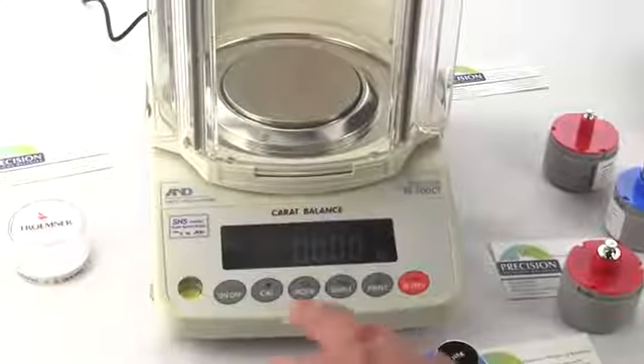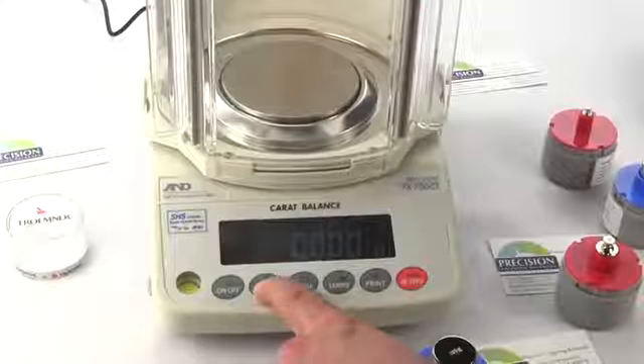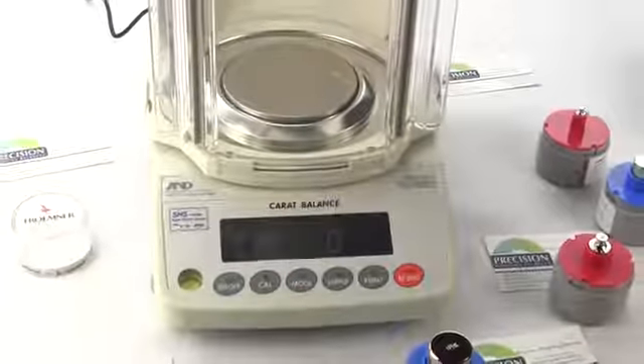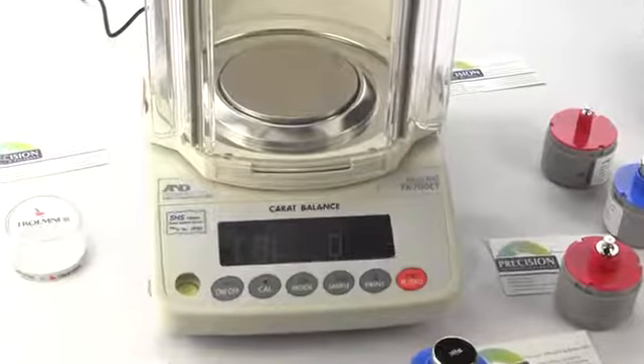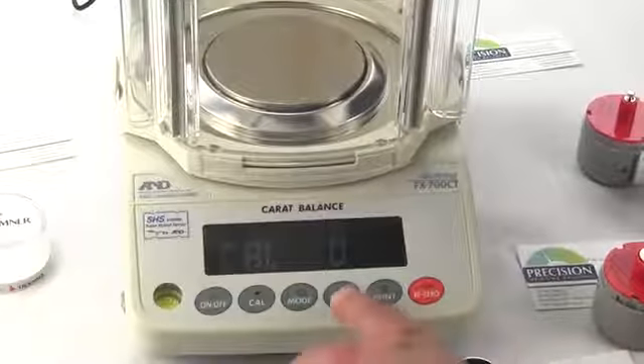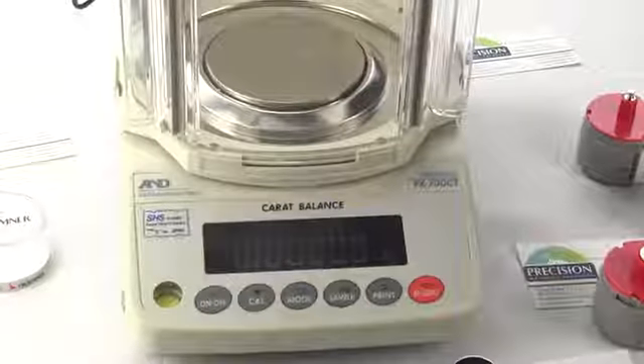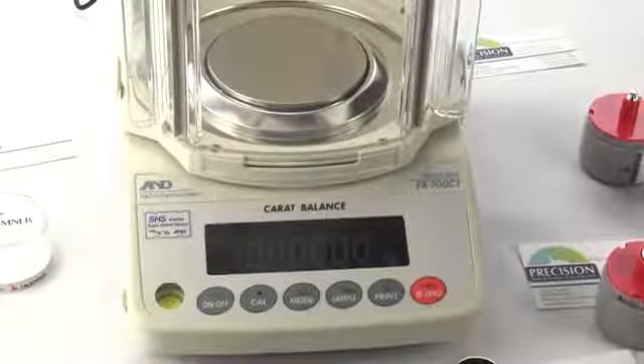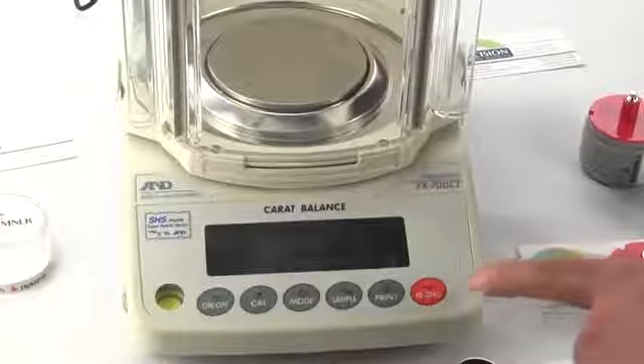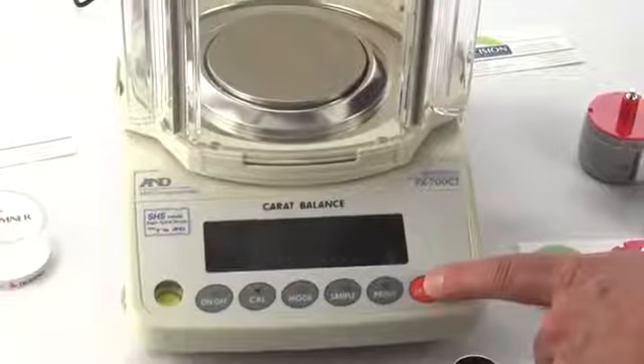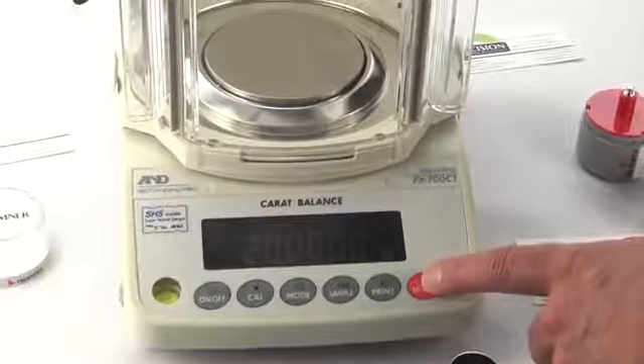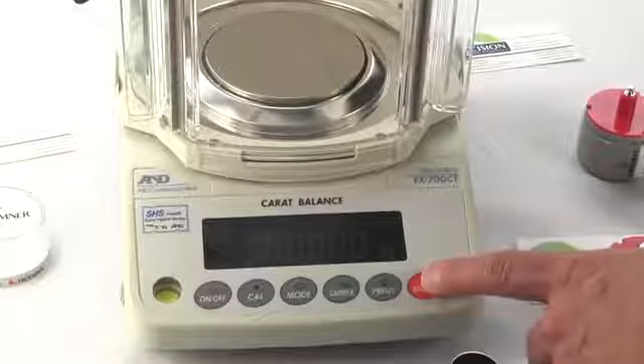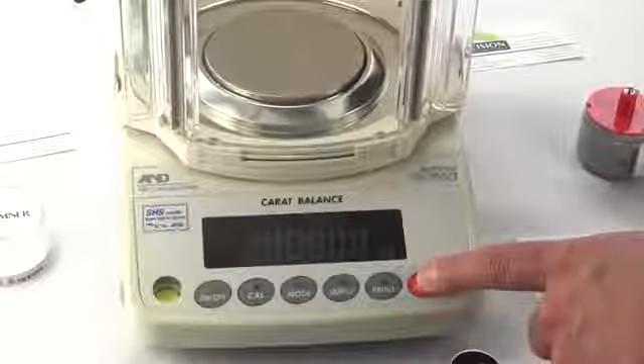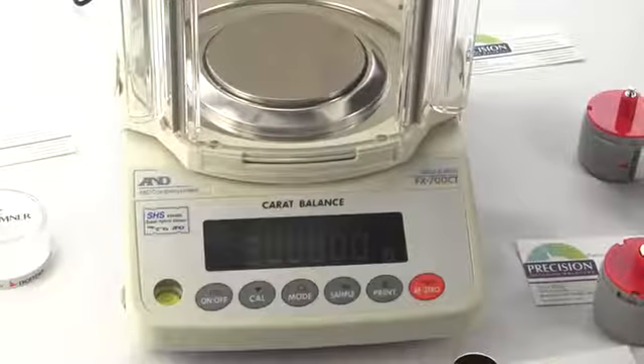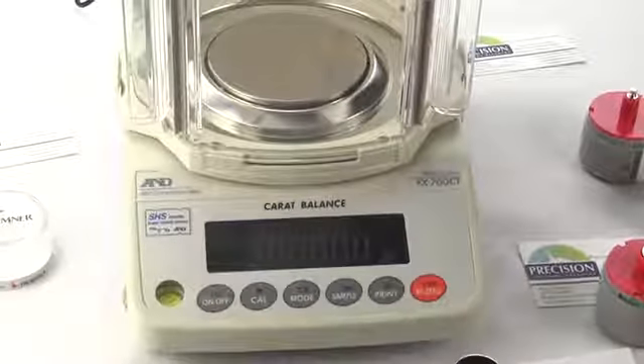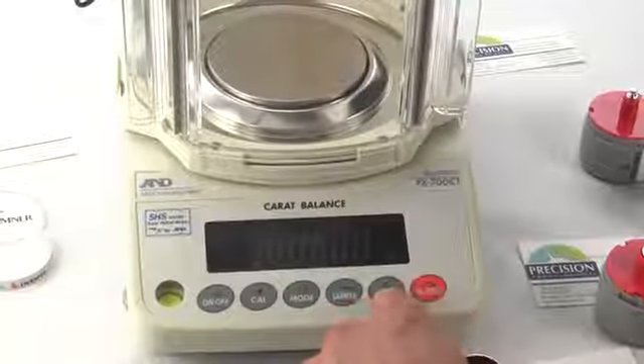So what one does is, again, we're going to go into the cal mode by pressing the CAL key. You'll see CAL OUT, and then you'll see CAL 0. So instead of hitting the PRINT key this time, we'll hit the SAMPLE key. And so 100 flashes. This is the default. If we want to change this, what we're going to do is press the RE-ZERO key, and we have now 150, 20, and 50. So you can just press the RE-ZERO. So this time we want to use 50. And so it flashes. We want to store that value. So to do that, we're going to hit the PRINT key.